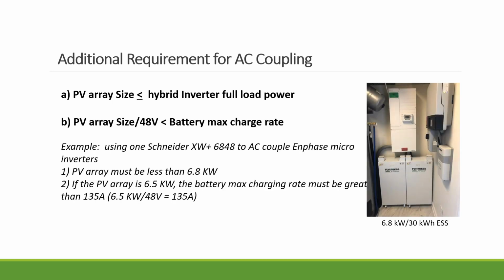If you AC couple a system, there are a few rules you want to follow. I'm sure a lot of you know the difference between AC and DC coupling, and we cover that in our other training section. Now, AC coupling has one weakness, and this is not a secret. No matter which solution you install, when the grid goes off and your battery is fully charged, and you are not home, on a sunny day, your PV inverter is going to produce more than your current load needs. In that case, through the frequency shift, the hybrid inverter will ask the PV inverter to shut off, because there's no way to take that additional power. Then they have to shut the PV inverter off. And that's pretty annoying, to be honest.